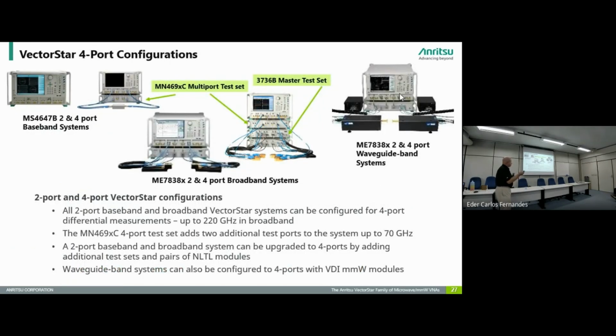And then we can expand to 4 ports. So now you see all of the different possibilities, starting with the mainframe VNA, adding the extra 2 ports for a 4 port up to 70 gigahertz. Over here is the millimeter wave broadband version, again using the same test sets but different configuration to get up to a 4 port 220 gigahertz. And we can do the same with the waveguide banded system with the VDI modules. It could be 2 or can be up to 4 as well.